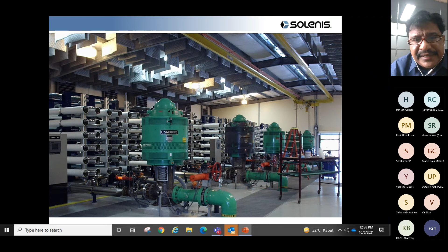So somebody thought, why do we waste that energy? So we take that reject and drive an energy turbine driving system. You pass the feed water to this energy driving device and pass the reject with that high pressure, thereby reducing the power consumption of the RO plant, because the major consumer for the RO plant is the power. So these are all technologies which have come up.